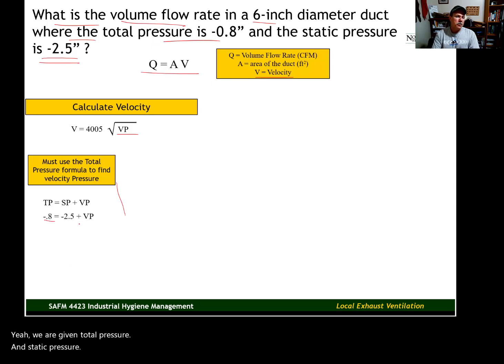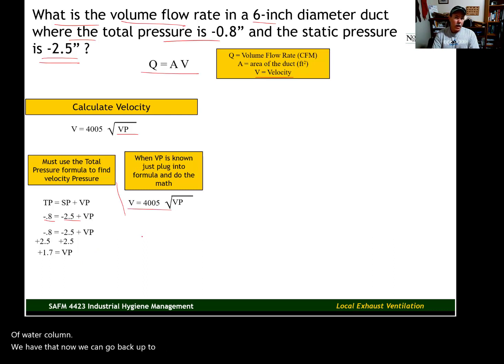Plug in our total pressure, plug in our static pressure, and solve for velocity pressure. We add 2.5 to each side. Our velocity pressure is 1.7 inches of water column. We have that. Now we can go back up to this formula and calculate our velocity.